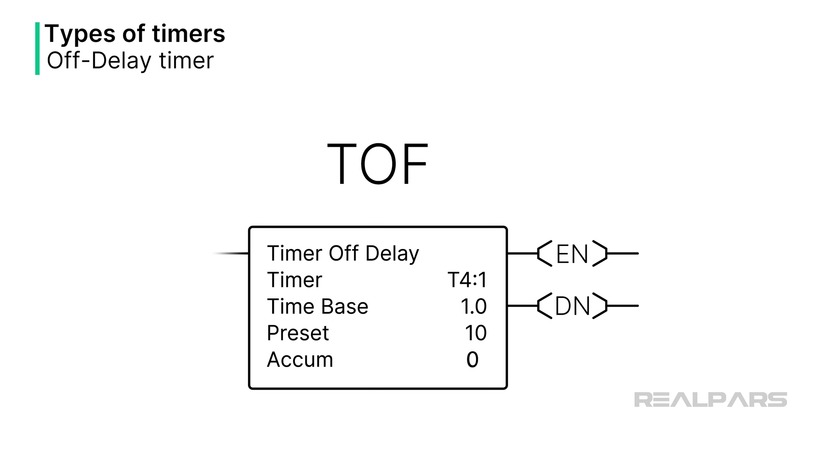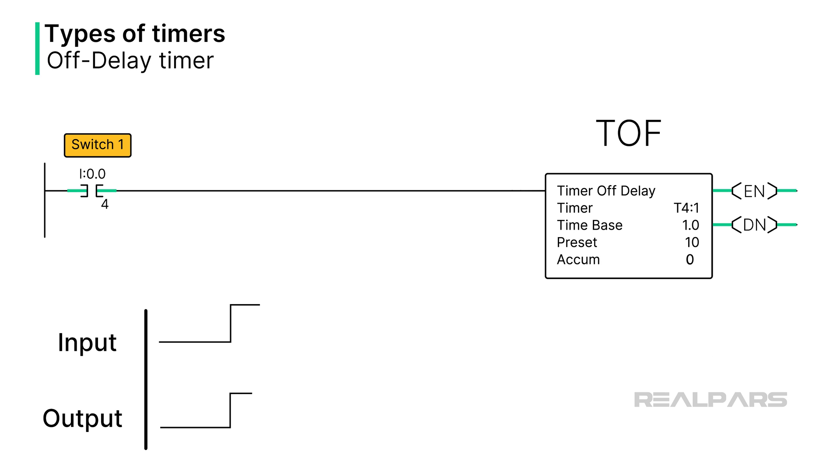An off-delay timer acts somewhat in the reverse of an on-delay timer. Once the timer rung goes true, the done bit is set immediately. When the timer input goes false, the timer begins to time, and after the preset is reached, the done bit turns off. This type of timer is useful for delaying an action until a certain time period has elapsed.